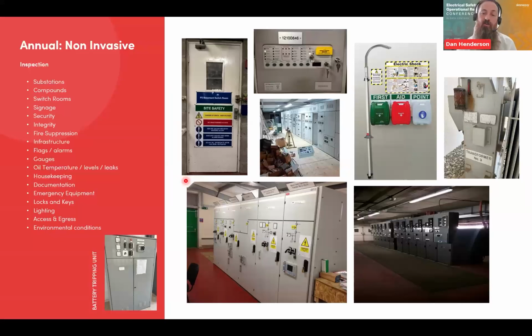They might keep documentation and drawings that are not relevant to anything in that room, might be relevant to the process. The point is you only want people going into the rooms to interact with the equipment that's in there. So you only want to be going in there for your visual inspections, or if you're switching the equipment or maintaining the equipment. The more time you're in there, the increased probability is of you being in there when something goes wrong. So in reality, the fewer interactions you have in there, the less likelihood is of you being around when something goes wrong. So we're trying to only have the right people in there with the right authorizations, with the right competence when they need to go in.